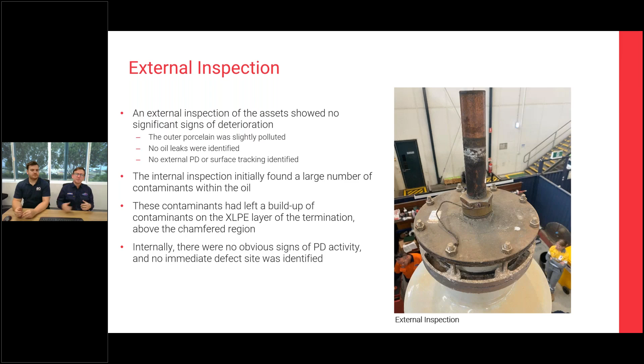So the internal inspection: I won't go into how cable terminations are designed, but essentially, as you look at the cable termination, there's an outer porcelain, in this particular installation with a silicone internal oil, and then the cable termination itself from the conductor is chamfered outwards onto the XLPE, and as you get towards the lower end of the termination, there is a semicon stress cone which helps grade the voltage that needs to decay as we progress further into the termination. As you can see, there's a clear identified contamination region on that photo there. That's looking at the very top part of the cable where it's chamfered down. On that chamfered section is where most of the contamination is noted.